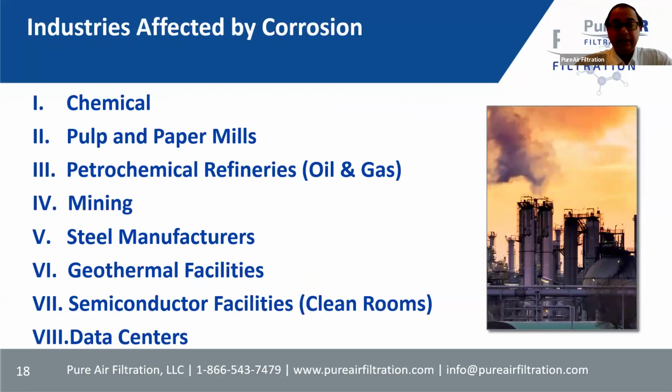The effects of gases in a controlled environment can be destructive. Corrosion can happen on your PCBs, the circuit boards, which accounts for 30% of equipment failure in industrial applications. Damage includes electrical damage, such as electrical current issues or loss of signals. Acidic gases are the most harmful. Rapid changes in temperature and humidity will accelerate the corrosion.